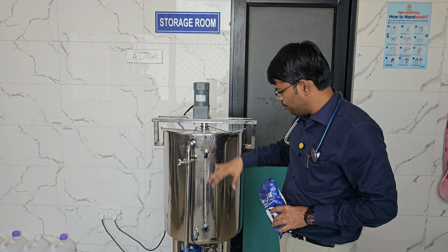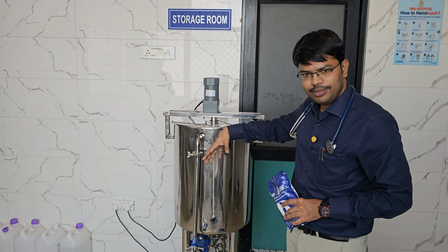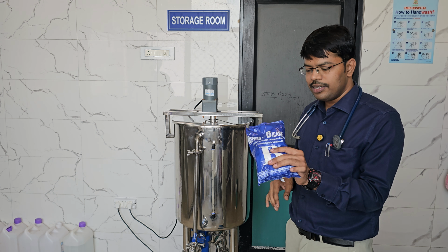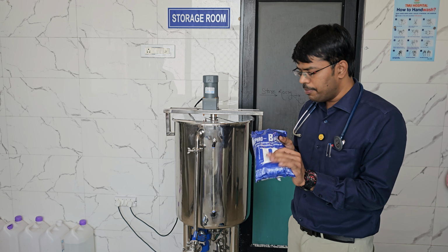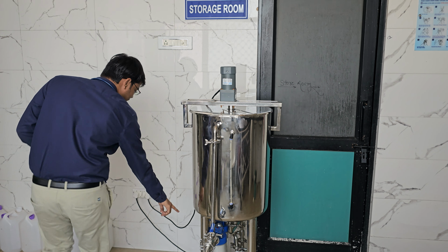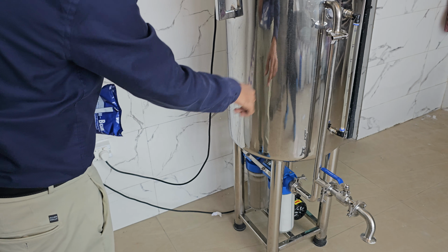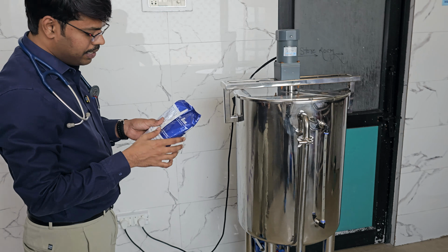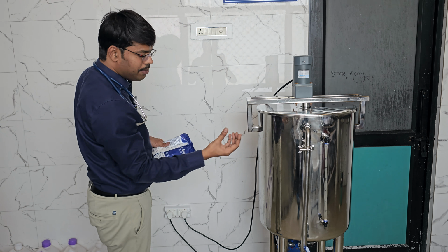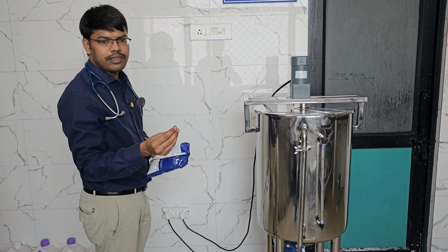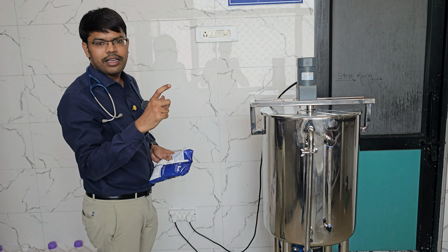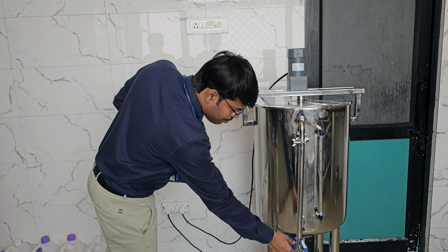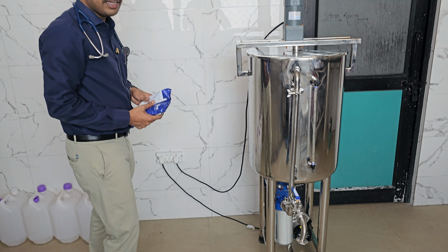This container has two pumps. Basically, the pump mixes it so that there won't be any debris. If any debris or waste is unfortunately present in the packet, it will be filtered out from this side. There are two filters here, so the mixing will be regular and the bicarbonate and water form a uniform solution, similar to IV soda bicarb. Once the solution is formed, we can take the output through this one. You open it, and it will come into the container.